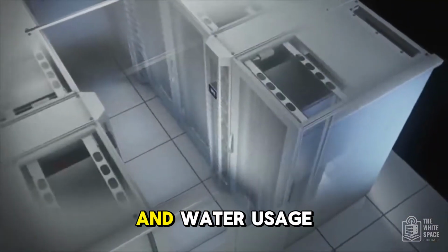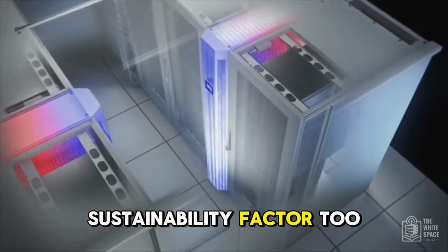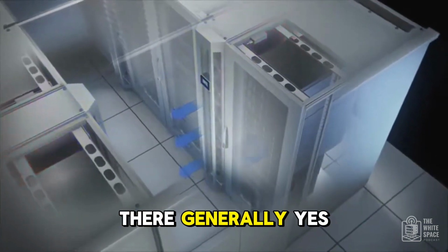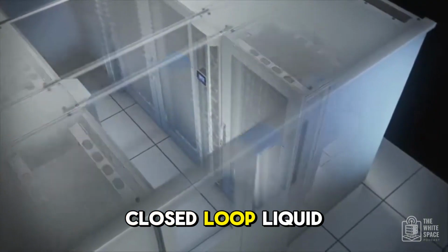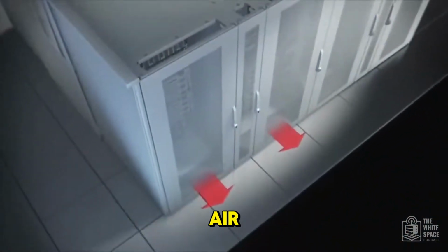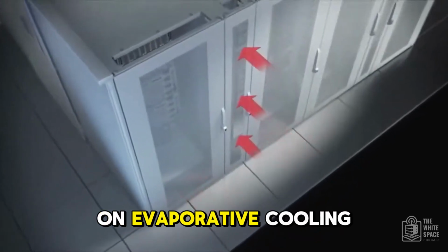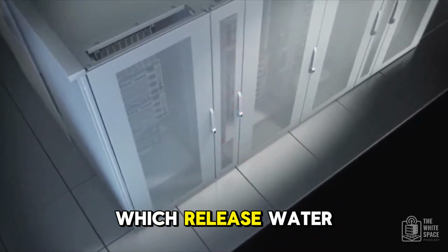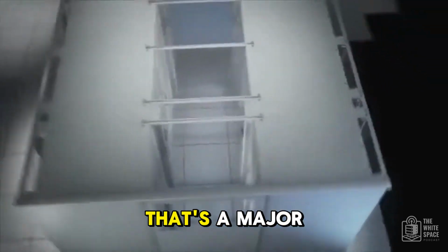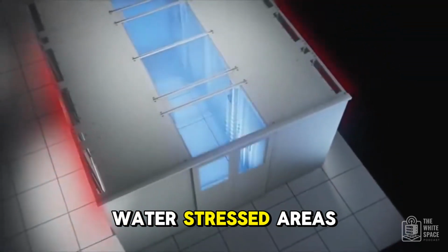It's complex. And water usage remains a big sustainability factor, too. Liquid cooling helps there. Generally, yes. Closed-loop liquid cooling systems inherently use far less water than air cooling systems that rely heavily on evaporative cooling towers, which release water into the atmosphere. That's a major plus, especially in water-stressed areas.